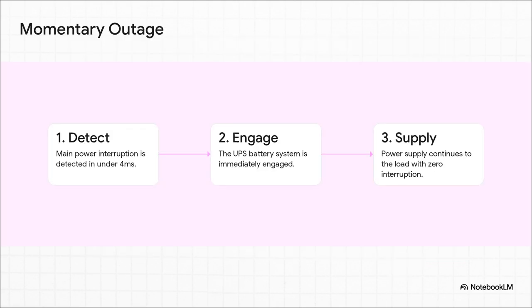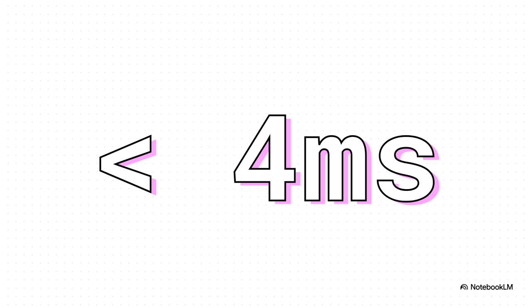Okay, let's start with something small, like a momentary power flicker or a sag from the grid. The instant the system detects any kind of irregularity, the UPS batteries kick in. And there's absolutely zero gap in the power supply to the equipment. It is completely, totally seamless. And when I say instant, I really mean it. The detection and the switchover to battery power all happen in less than 4 milliseconds. Now, to put that in perspective for you, a single blink of a human eye takes about 100 to 400 milliseconds. This system reacts dozens of times faster than you can even blink.